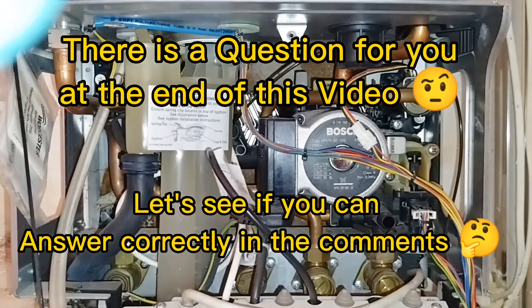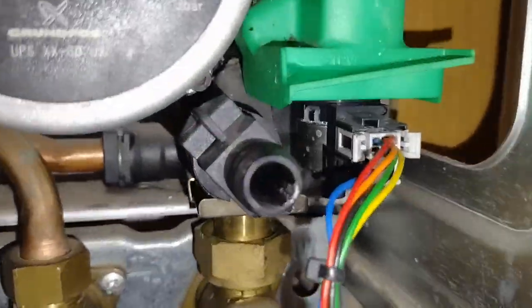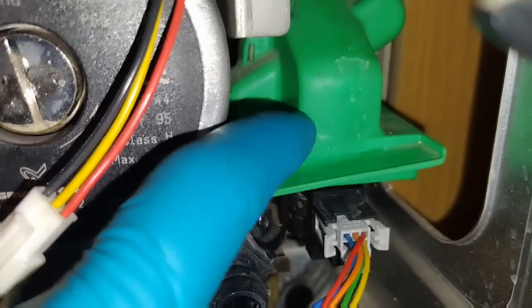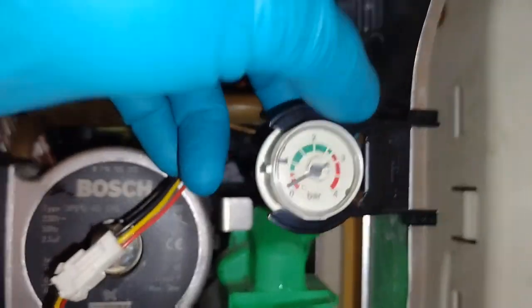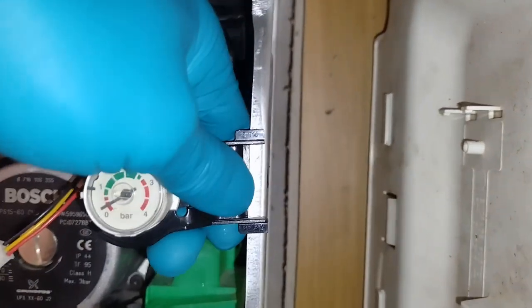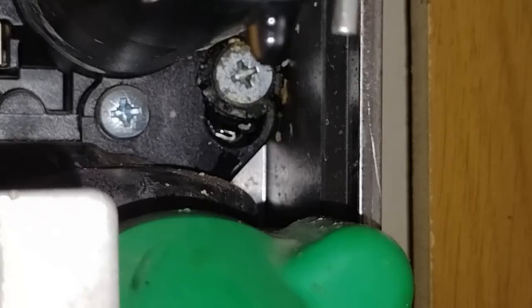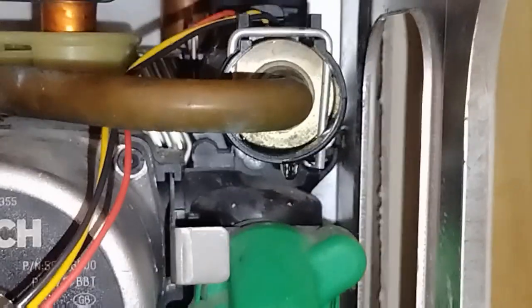In this one we're going to look at another problem which occurs in a junior model, a Worcester Greenstar combination boiler. If you see a leak coming from the right hand side manifold, which is the return manifold of the boiler, you can very easily, as most people do, mistake it for a leaking turbine or a turbine adapter. But if you see a leak or marks, especially at the back of this manifold, a build up of limescale and whiteness at the back, mostly around the top back of this manifold, then it would almost always mean that the manifold itself has started to leak from the manufactured joints, and it's not something which is repairable, so you will have to replace the manifold itself.